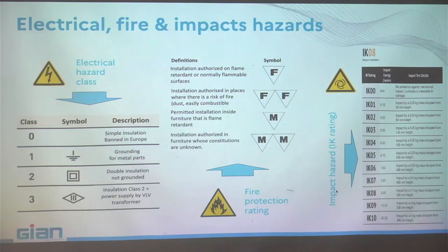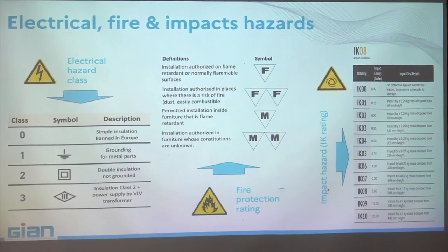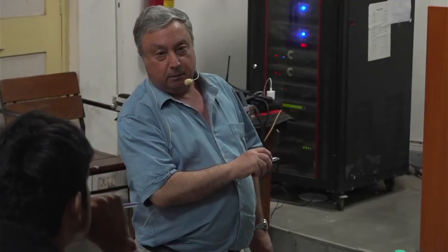Now be careful, because 48 volt, if you touch it, you will have a serious shock. And if you have water in the floor and you are not having insulating shoes, then you may be even dead. More than 20 volts when you are in the water is a huge problem. In the swimming pools, this is an obligation, okay? Unless you want to kill some people that you invite at home.